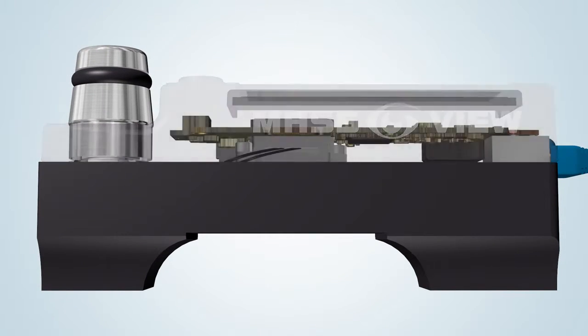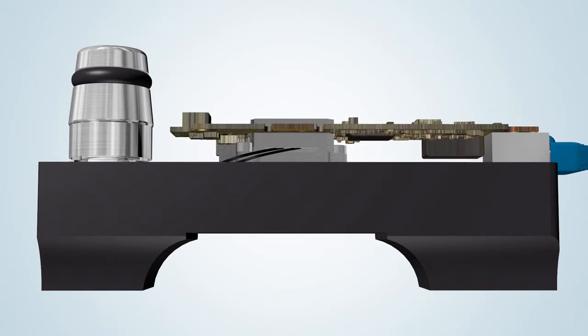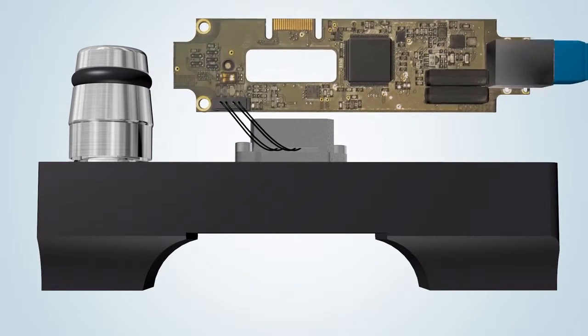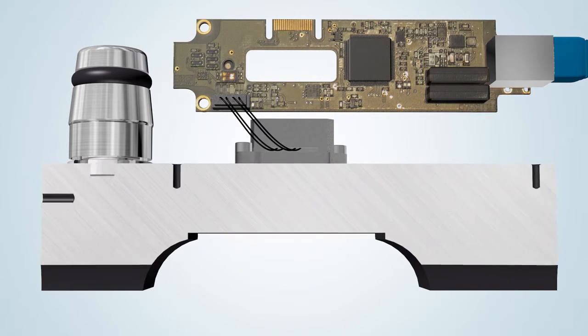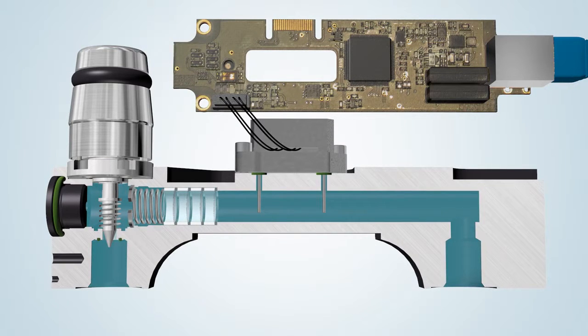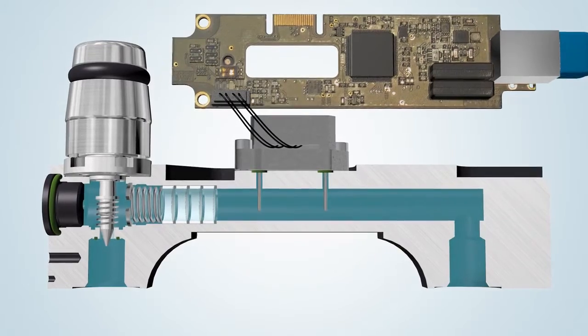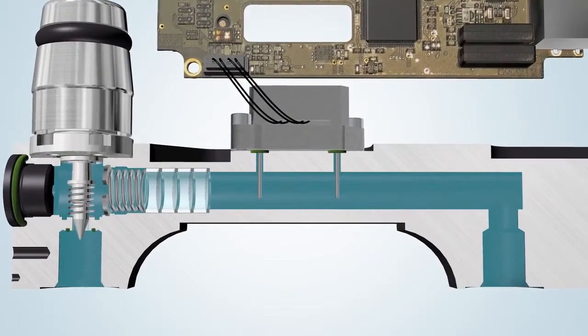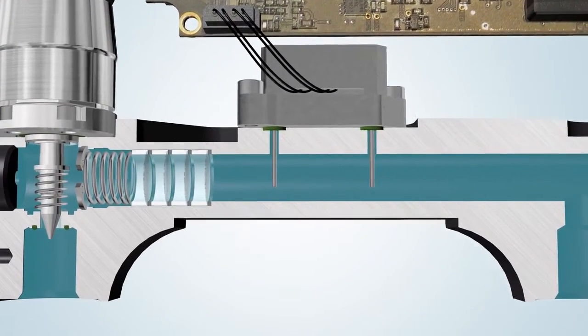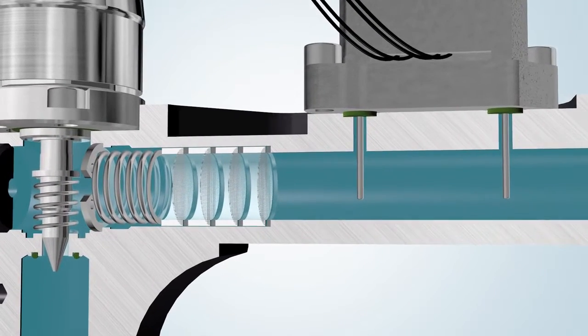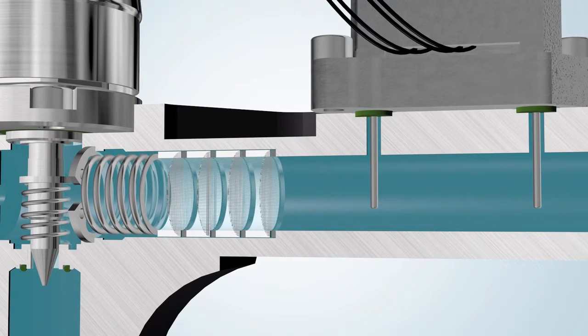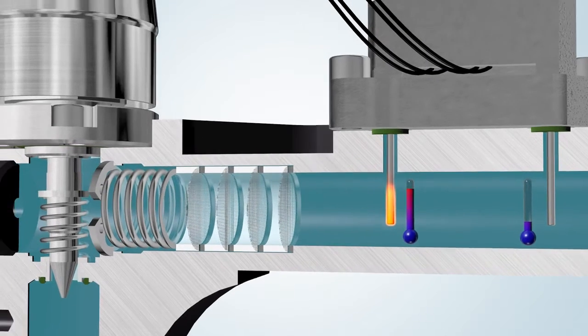Under the cover of the MassView is the electronics board using surface mount device technology. The measuring part of the instrument consists of a flow straightener element combined with the thermal inline mass flow sensor. The flow sensor consists of two stainless steel pins encasing the heater in the first probe and the temperature sensor in the second probe. A constant temperature difference, or delta T, is created between the two sensor probes.